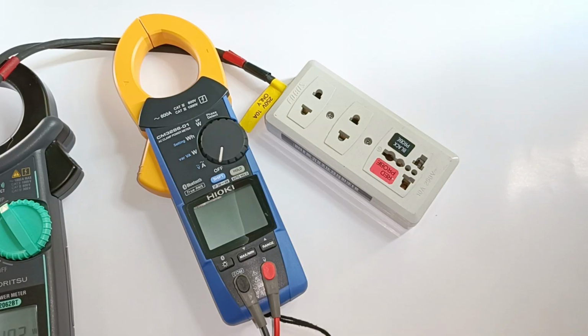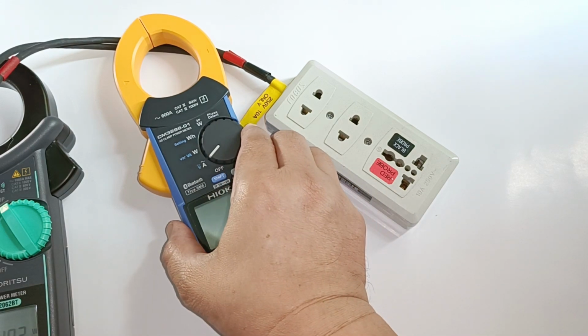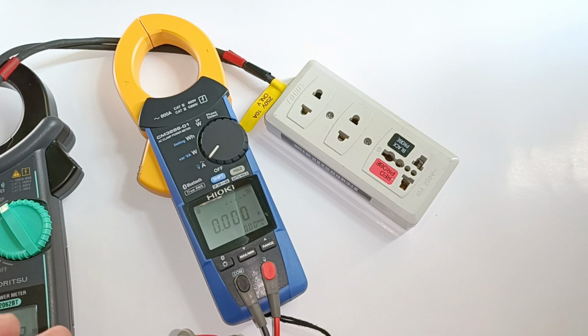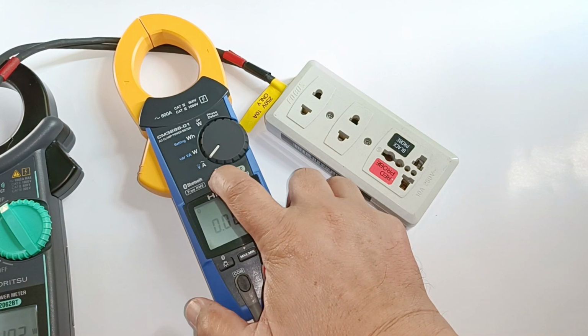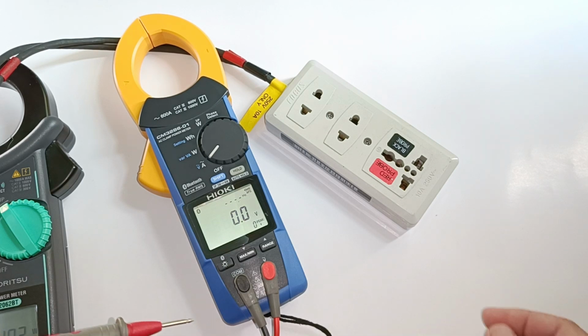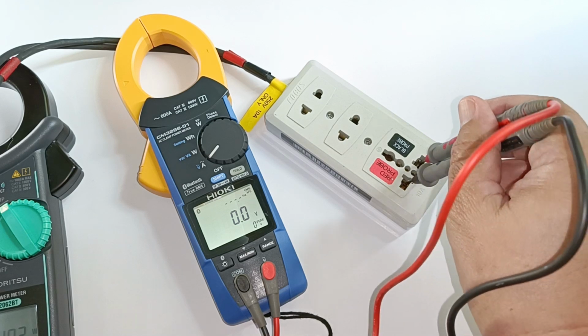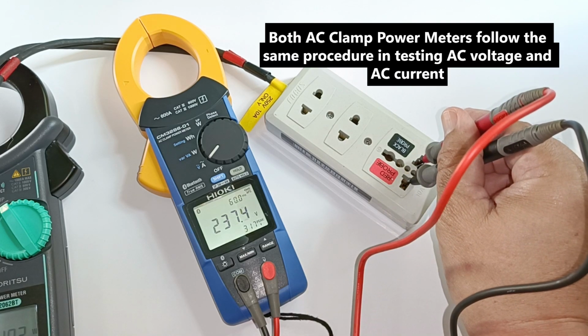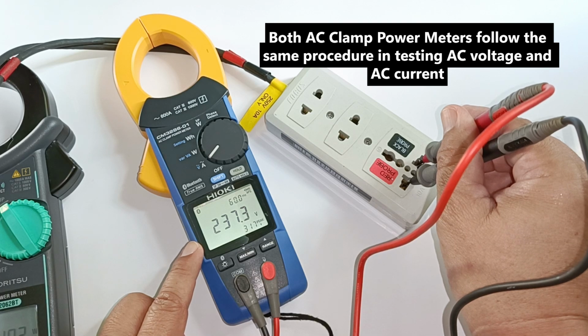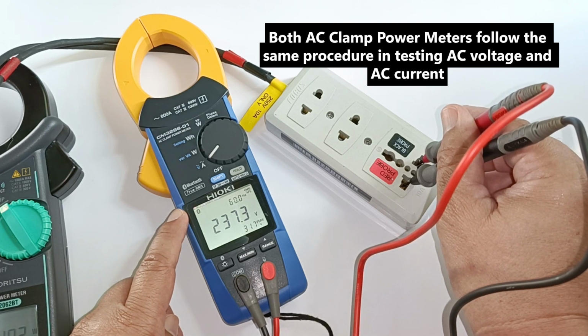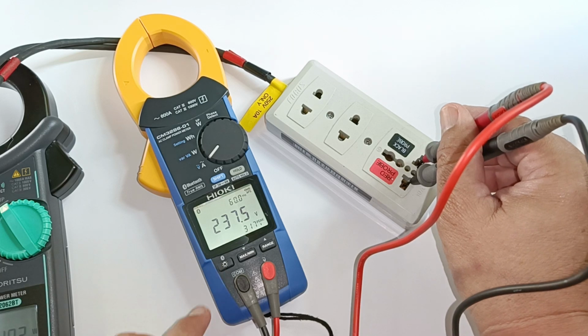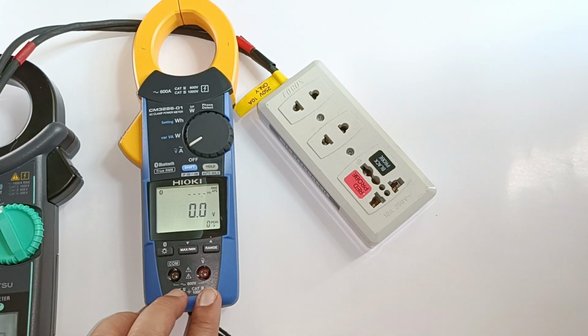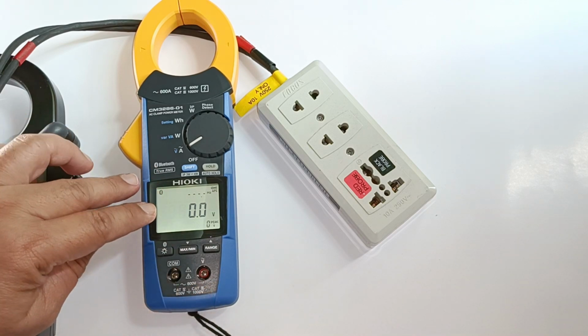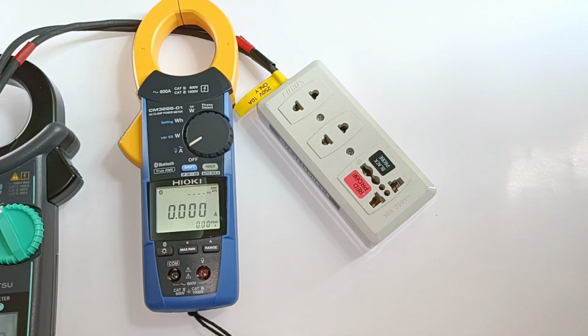Let's make a simple AC voltage measurement. To do this, the procedure is the same with the standard clamp meter. Just turn the function selector to AC voltage. Connect the test leads to the test points. Here I have a reading of 237.4 volts at 60 Hz with peak at 317 volts. To measure AC current, remove the test leads and select the AC current test function.